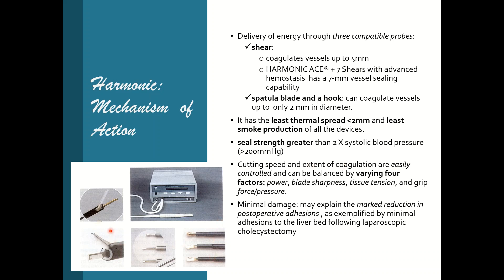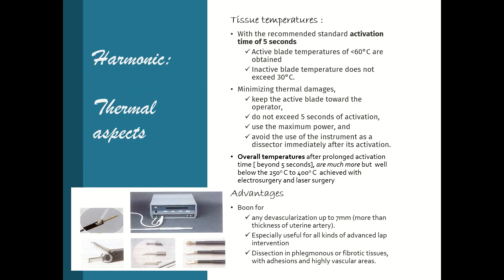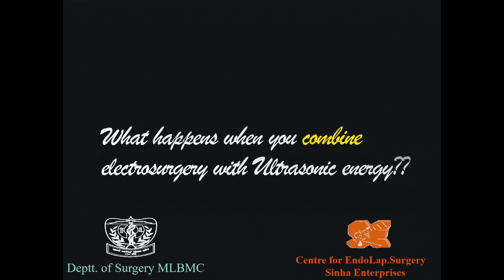Cutting speed and extent of coagulation depend on four factors: the power applied, blade sharpness, tissue tension, and grip force. The minimal tissue damage by the ultrasonic source explains the marked reduction in post-operative adhesions. If a patient needs re-exploration after a procedure done using Harmonic, minimal adhesions are found — another advantage of the ultrasonic energy source.